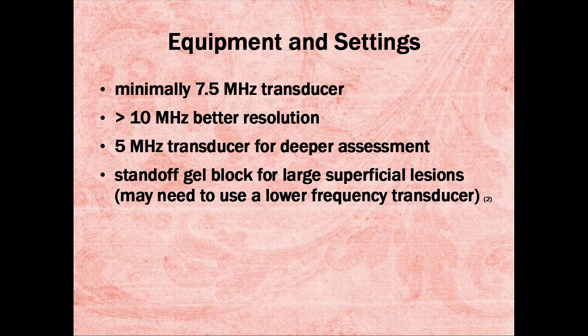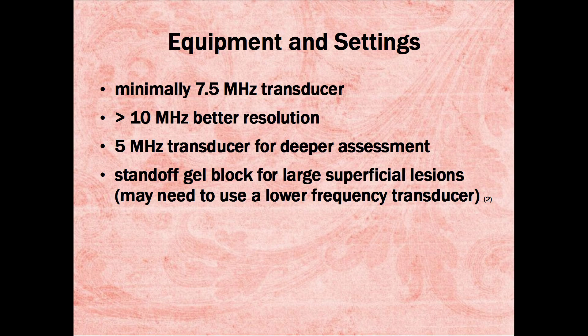Equipment and settings. Minimally, you need a 7.5 MHz transducer. Having a transducer of greater than 10 MHz will give you better resolution, but sometimes you need to use a 5 MHz transducer for assessment of deeper lymph nodes. A standoff gel block can be used for large, superficial lesions, but you may need to use a lower frequency transducer.